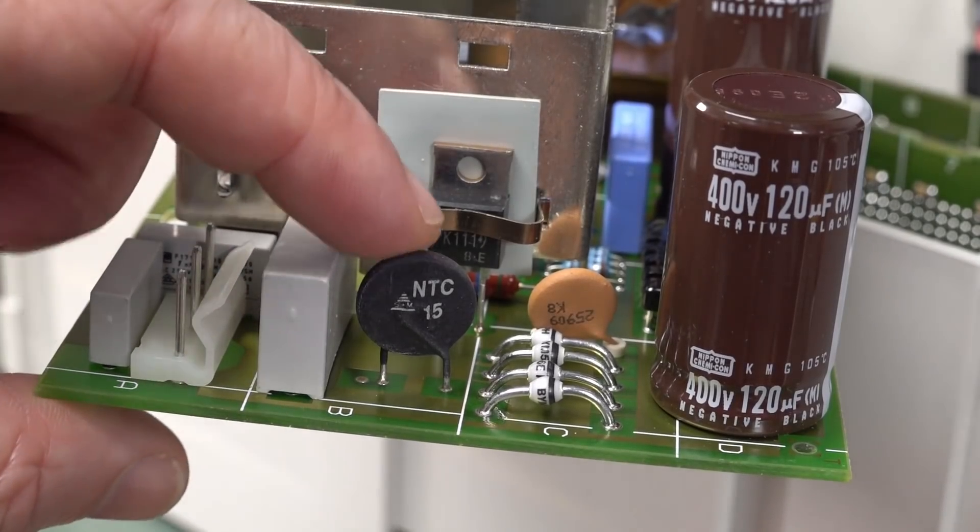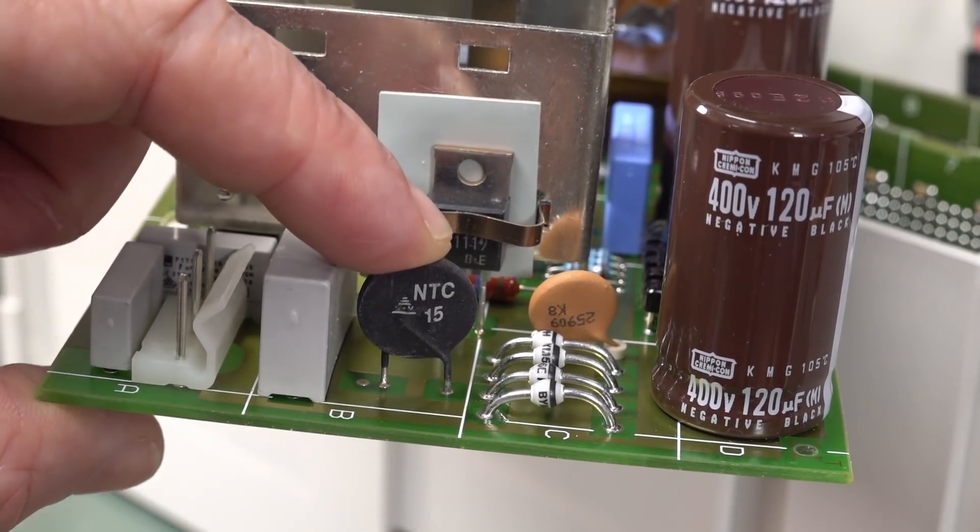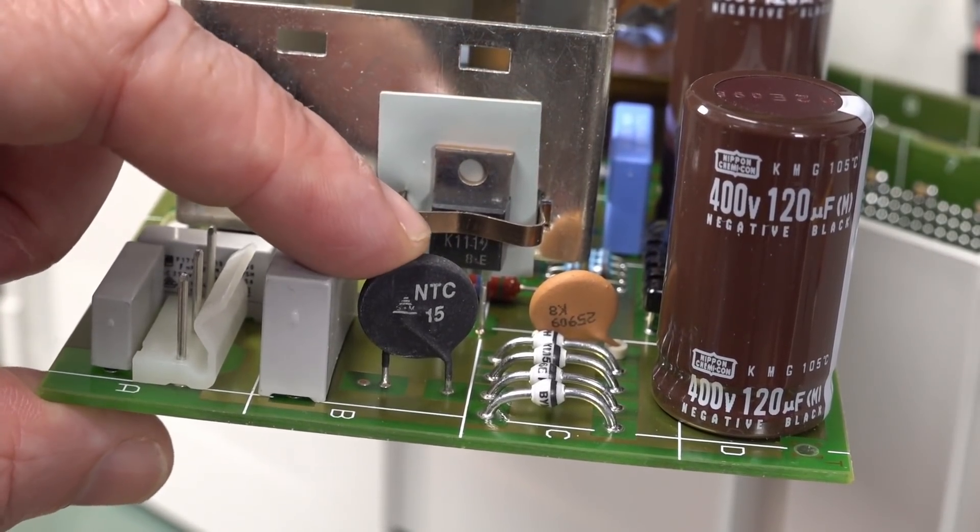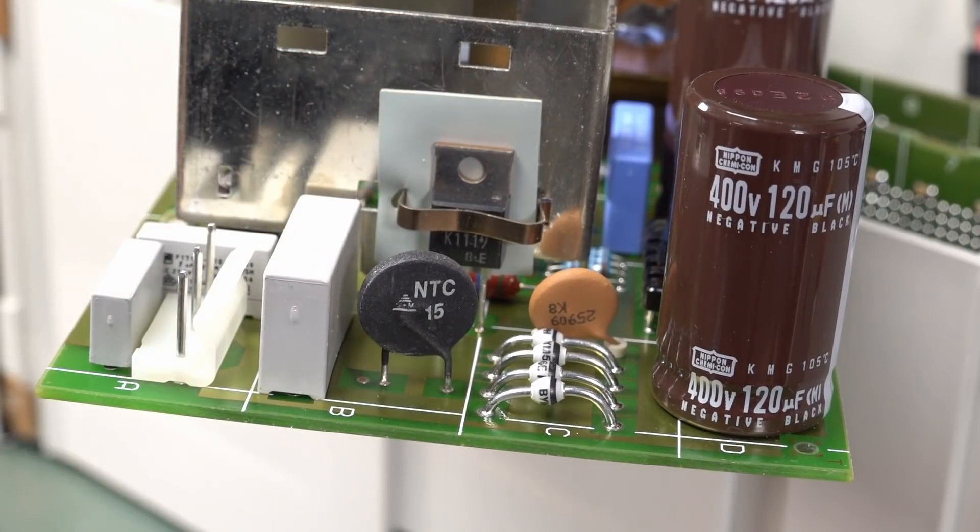Okay, there's the part there. And the first thing to notice, you know how I mentioned PTC before? This is actually NTC, Negative Temperature Coefficient. PTC is Positive Temperature Coefficient. I just assumed it was a PTC.